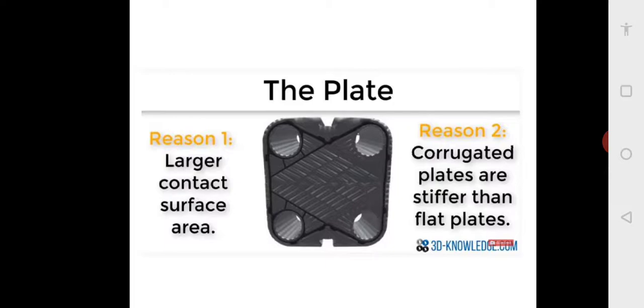You can see the larger contact surface — the plates are corrugated, not simple flat plates. Corrugation, like roof sheets, adds to the strength. Not only that, it also increases the turbulence, and thus the convective heat transfer coefficient H increases. So to increase Q — the heat transfer through convection — both H and A are increased. This is how plate type heat exchangers are far more efficient than shell and tube type heat exchangers.